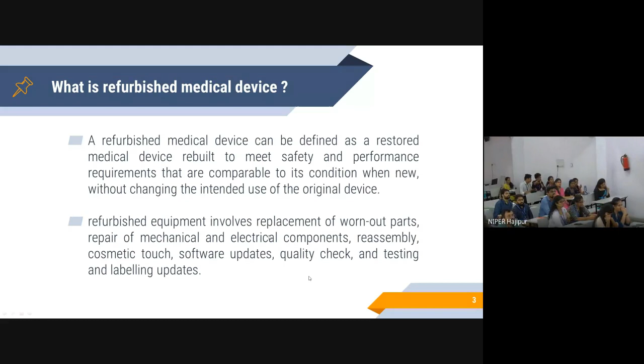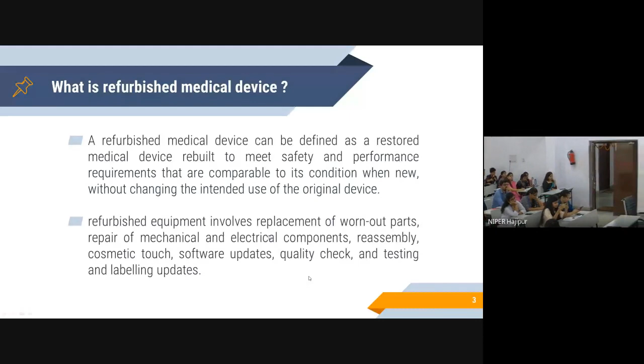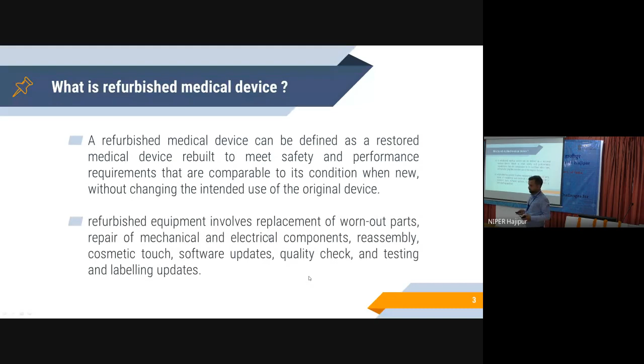Refurbished medical device can be defined as a restored medical device rebuilt to meet the same safety and performance requirements that are comparable to its condition when the device was new without changing the intended use of the device. Refurbished equipment involve replacement of worn out parts, repair of the mechanical and electrical refurbishment, some cosmetic touch like polishing of the device or painting of the device, software updates, quality check, and testing and labeling updates, including the user manual training document.